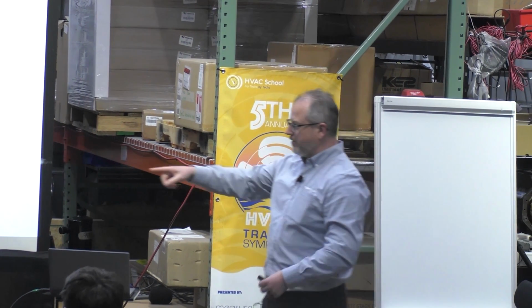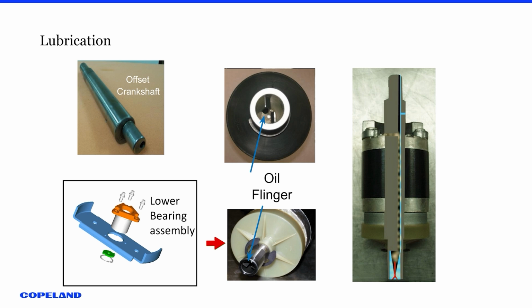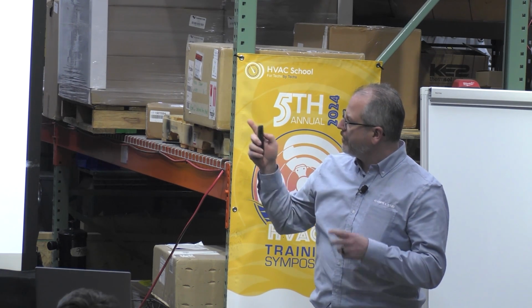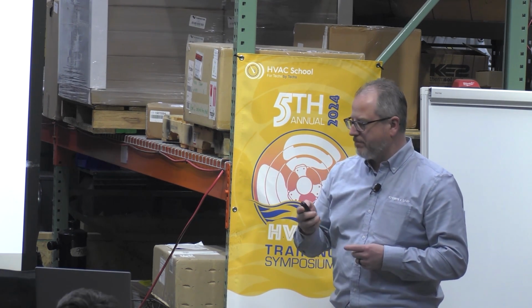So there's the little flingers that you were just talking about, right on the bottom. Those do pull right out if you wanted to. And you can kind of see the crankshaft, how it's off-centered. And when it rotates at 3,500 RPM with centrifugal force, it's pulling that oil right up, and it's going through the little journals, lubricating the parts wherever we need.